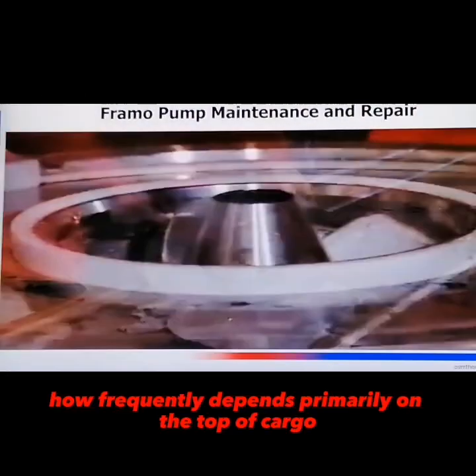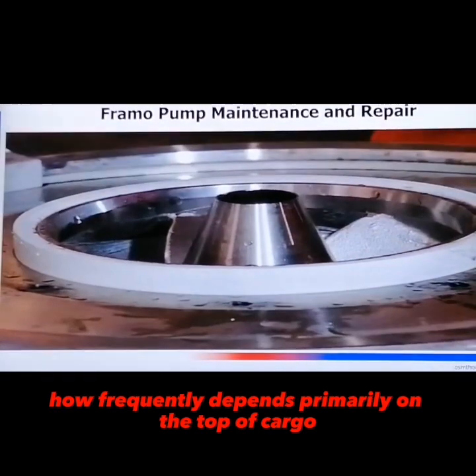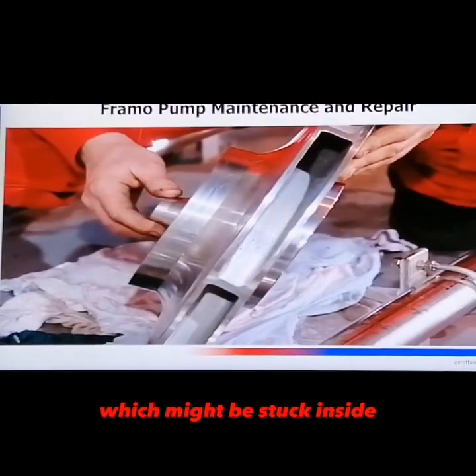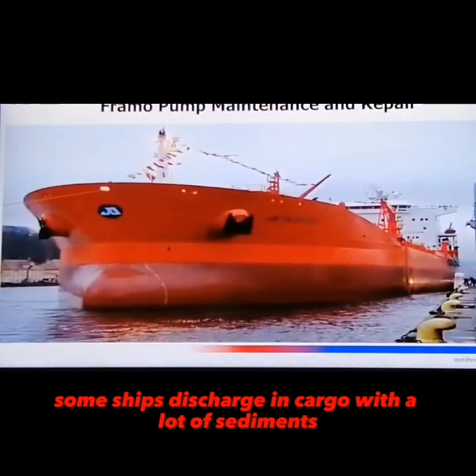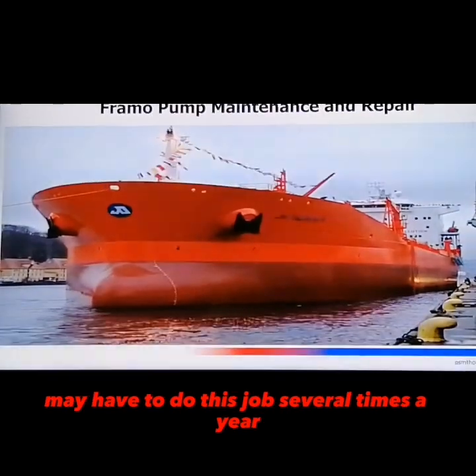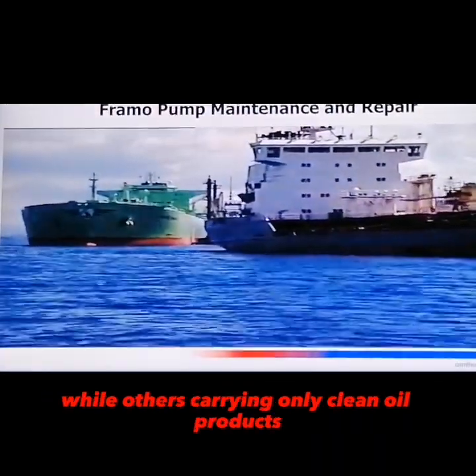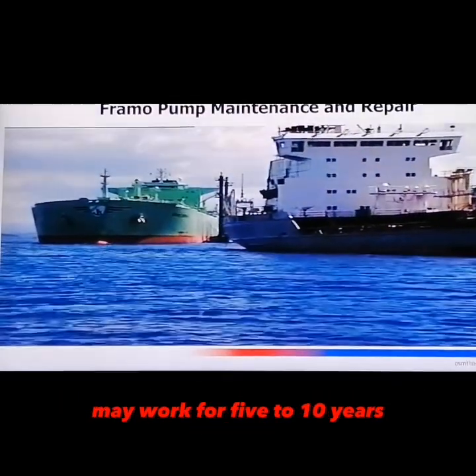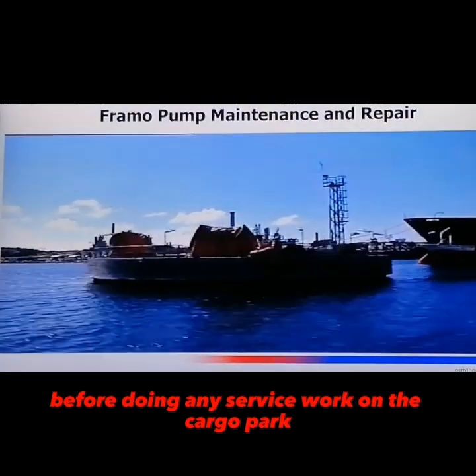Changing the wear rings is a service job normally done by the crew on board. How frequently depends primarily on the type of cargo. Check the impeller for any foreign particles which might be stuck inside. Some ships discharging cargo with a lot of sediment may have to do this job several times a year, while others carrying only clean oil products may work for 5-10 years before doing any service work on the cargo pump.